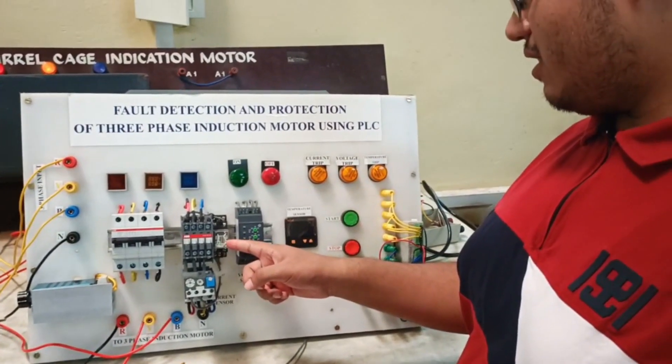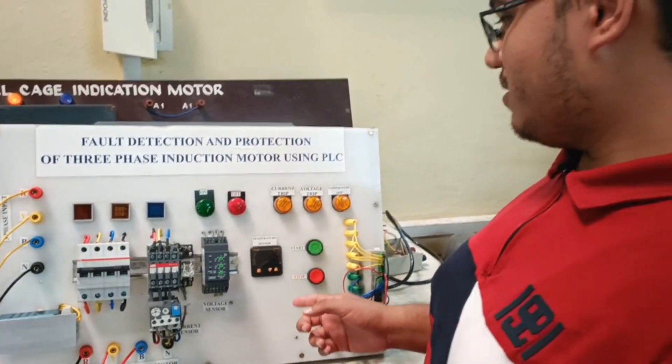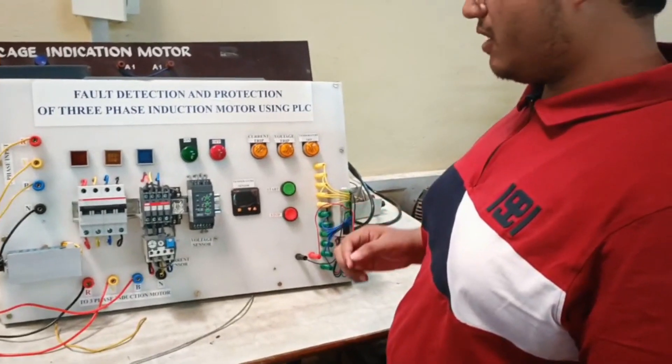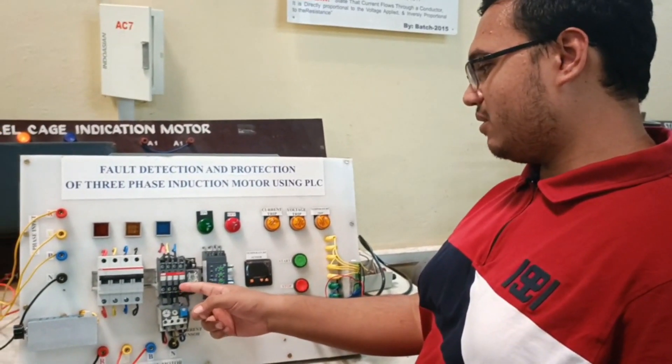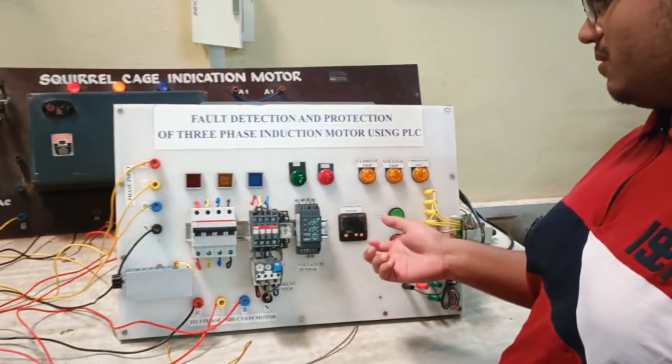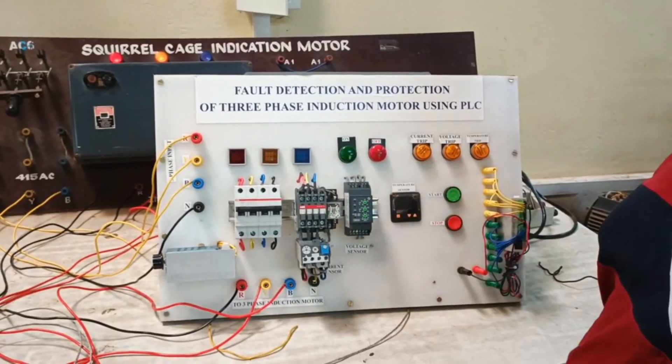This component is an auxiliary relay which we are using because this PLC runs on 24 volt while this contactor runs on 220 volt. Hence to fix the voltage we use this auxiliary relay.